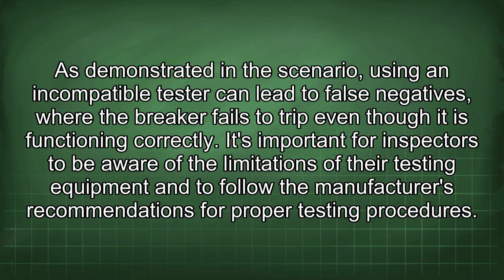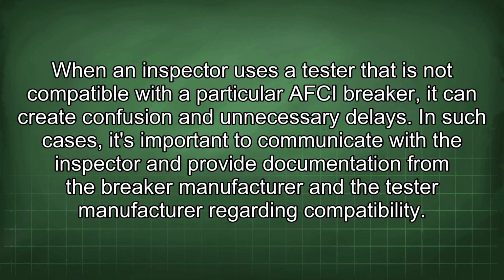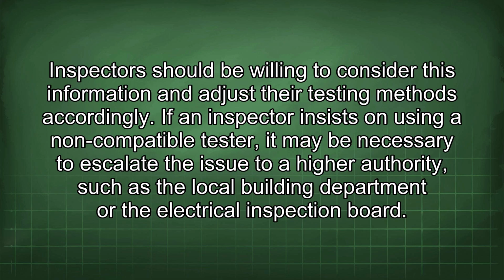It's important for inspectors to be aware of the limitations of their testing equipment and to follow the manufacturer's recommendations for proper testing procedures. When an inspector uses a tester that is not compatible with a particular AFCI breaker, it can create confusion and unnecessary delays. In such cases, it's important to communicate with the inspector and provide documentation from the breaker manufacturer and the tester manufacturer regarding compatibility. Inspectors should be willing to consider this information and adjust their testing methods accordingly.